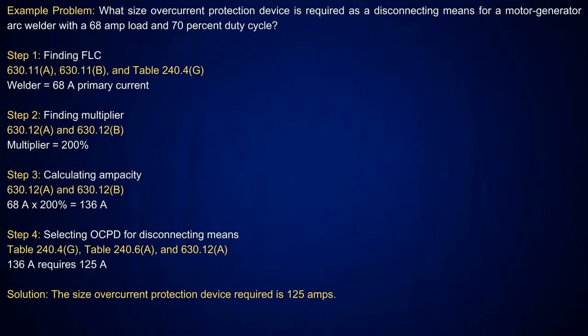Okay. So I've got a 68 amp load, and it has a 70% duty cycle. Now, if I was sizing the conductor, I definitely would use that 70% to size my conductor. But what we're trying to point out here is that all you need to do is size the overcurrent device, so I'm going to take it at 200%. If I take 68 amps at 200%, it says rated or set not more than 200%. That means I can't exceed it. So the next size below that 136 amps is a 125 amp overcurrent device.